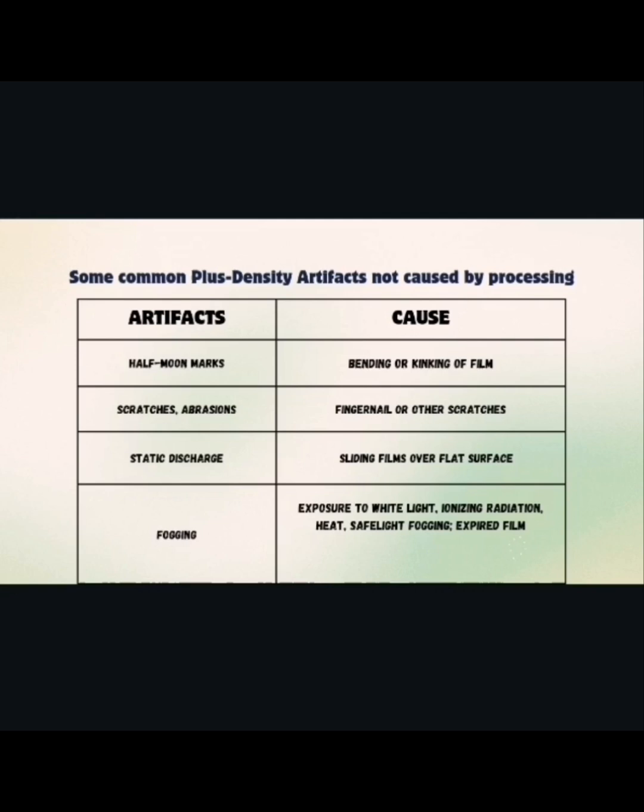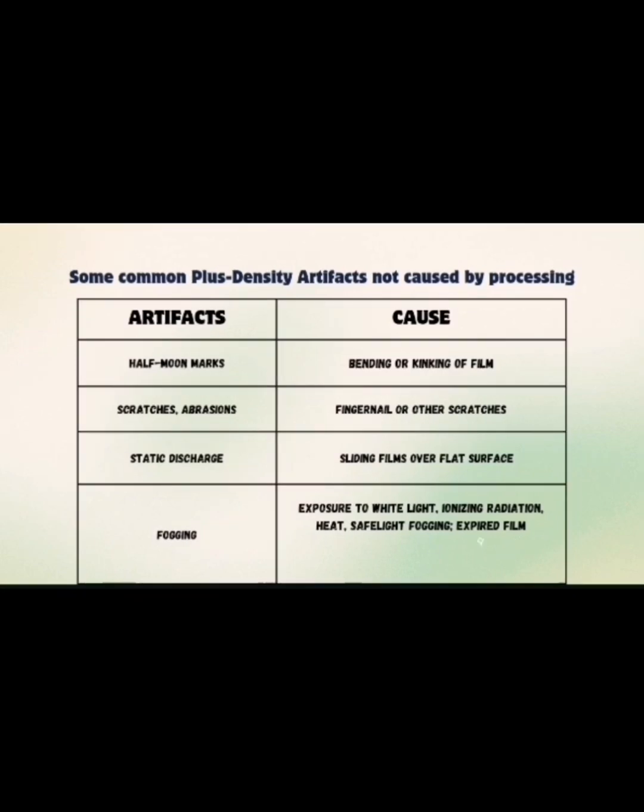Next is scratches and abrasions. The cause is a fingernail or other scratches. Static discharge, and the cause is sliding film over a flat surface. Fogging, and the cause is exposure to white light, ionizing radiation, heat, safelight fogging, and expired film.